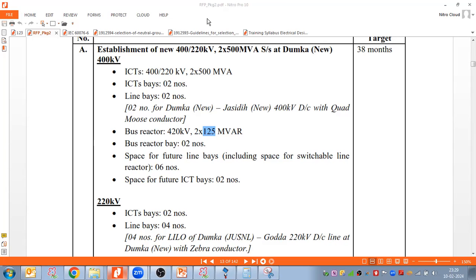So what about smaller substations? In this case, the load dispatch center would give us a code, and then we need to take action on it, whether to switch on or switch off. It is also our duty to inform the load dispatch center that the bus voltage is increasing. At our substation it was 420, and above 425 there was a guideline given — if it crosses 420, 425, you need to inform the load dispatch center also.